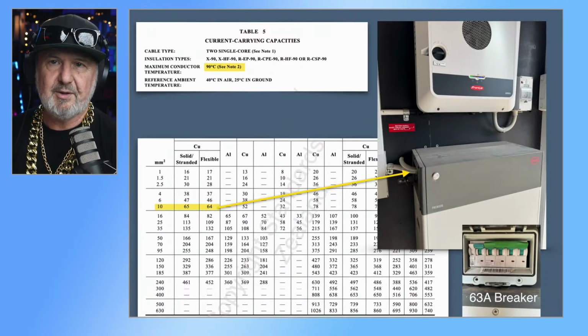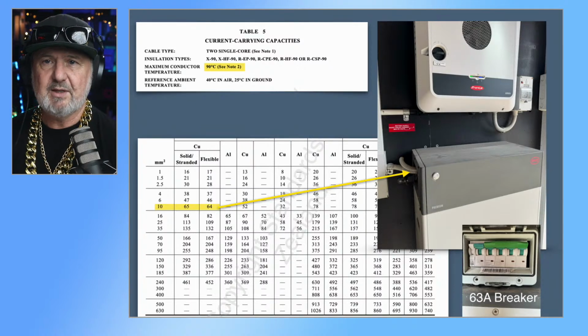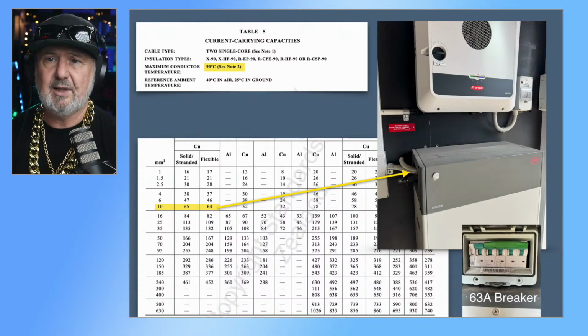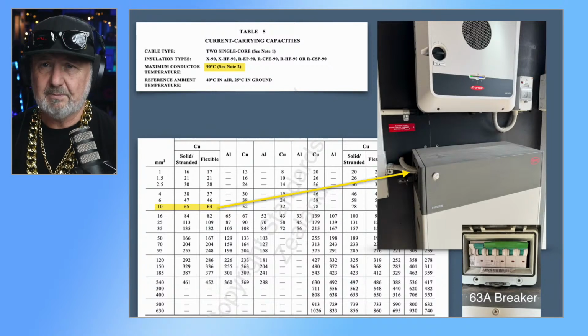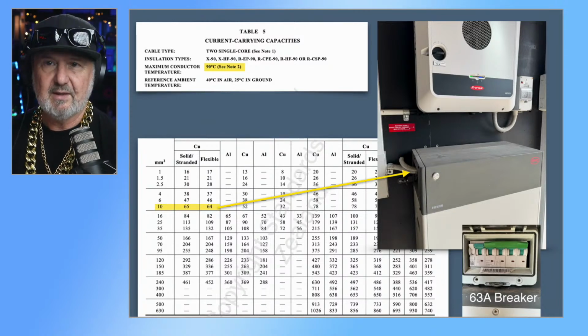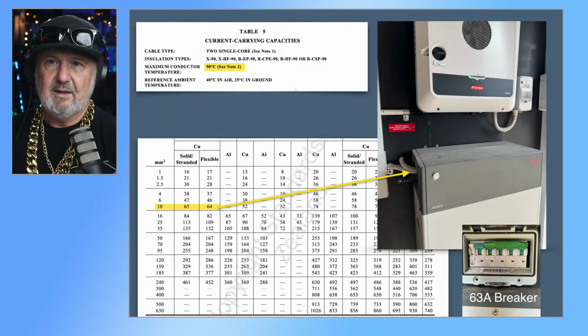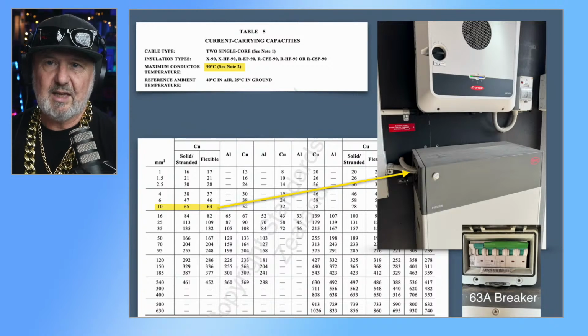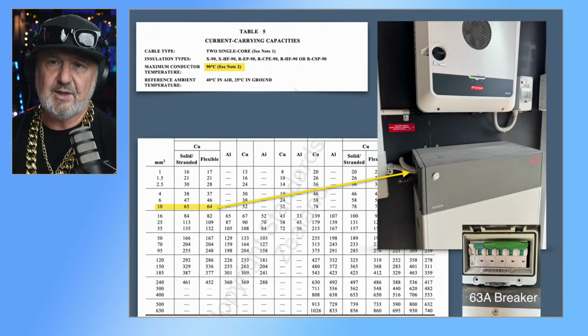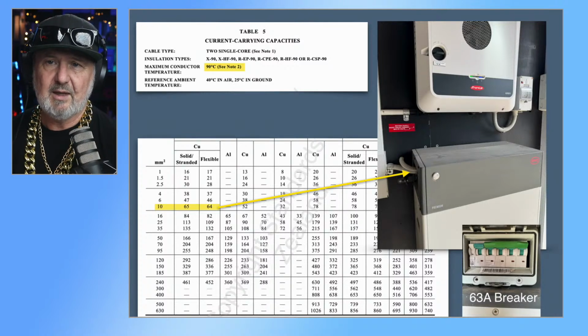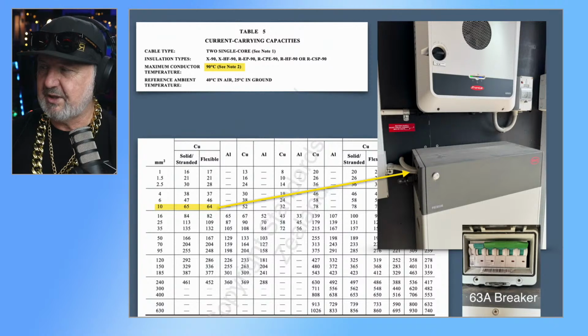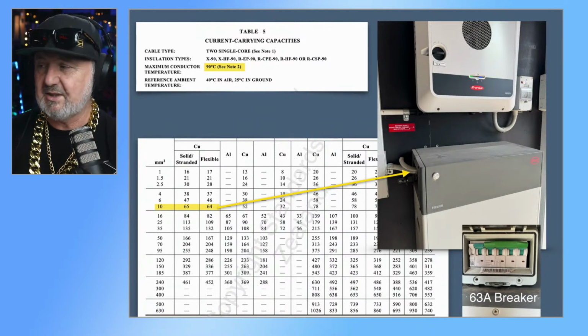So this is a very popular combo, the Fronius Gen 24. This is the 10 kilowatt 3-phase, and the BYD. It's a stack. I think it's a 11 kilowatt hour stack of battery modules here, and the BYD battery has an output breaker rated at 63 amps. So what you've got to consider is that even though the Gen 24 may draw a maximum, say 50 amps, you've got to rate the cables for the output overcurrent protection device built into the battery. So because there's a 63 amp breaker there, we've got to follow the requirements for protecting a cable, or select a cable that will be protected by a 63 amp breaker.